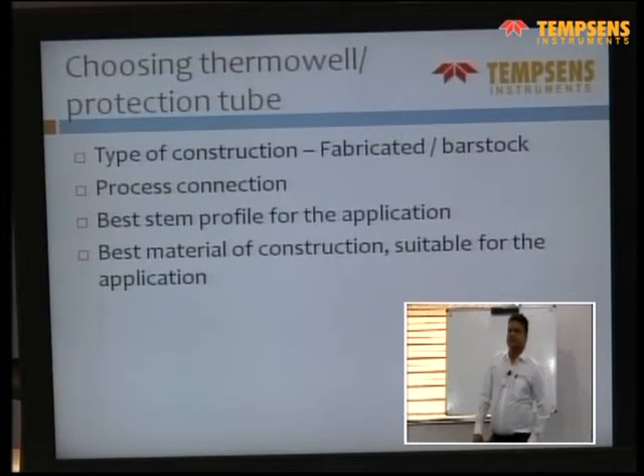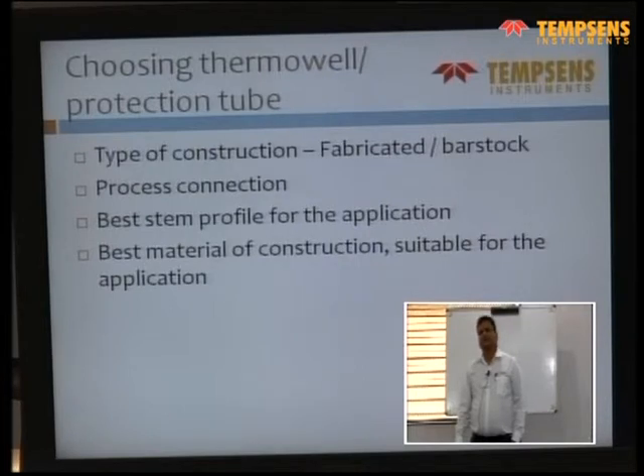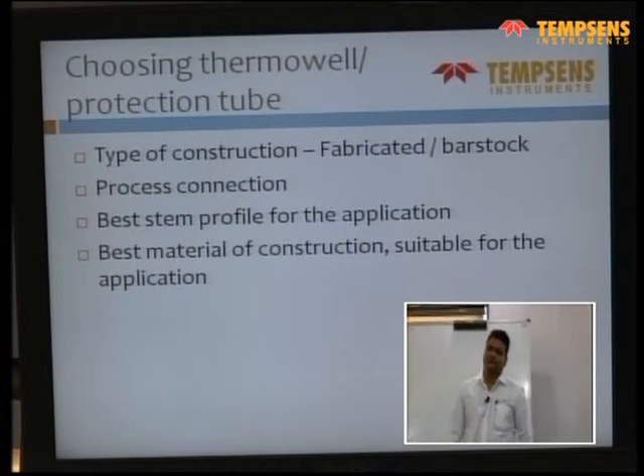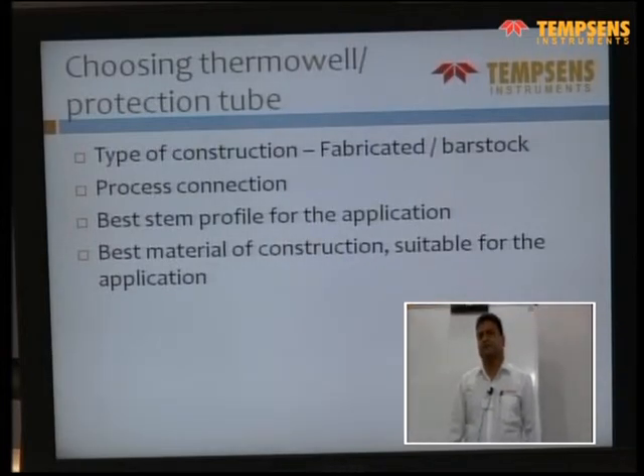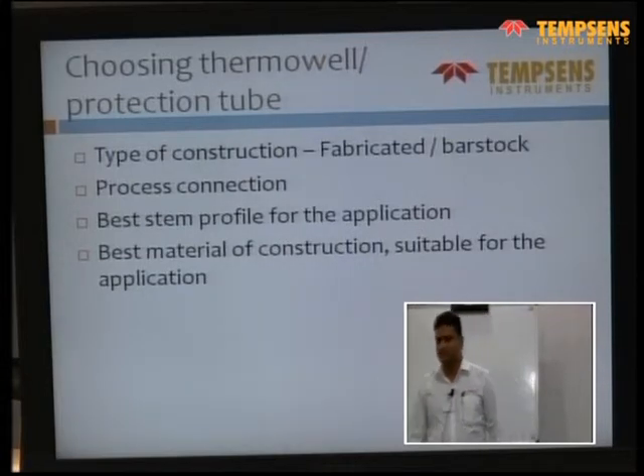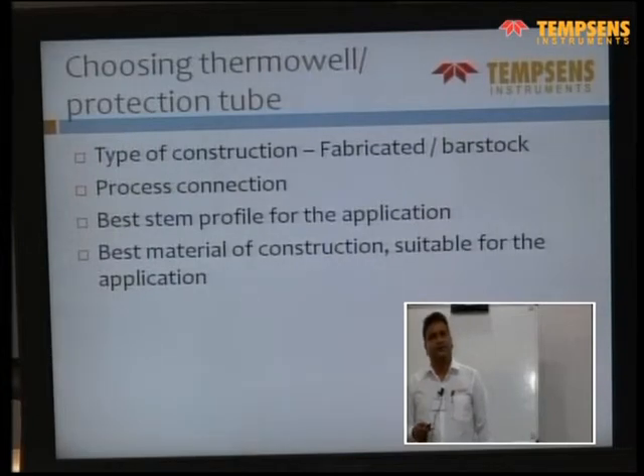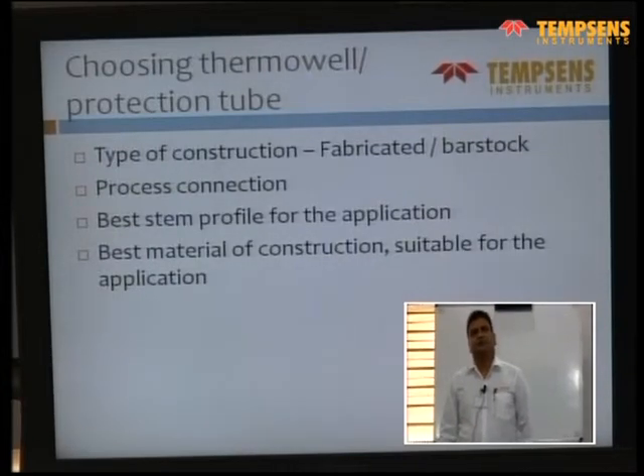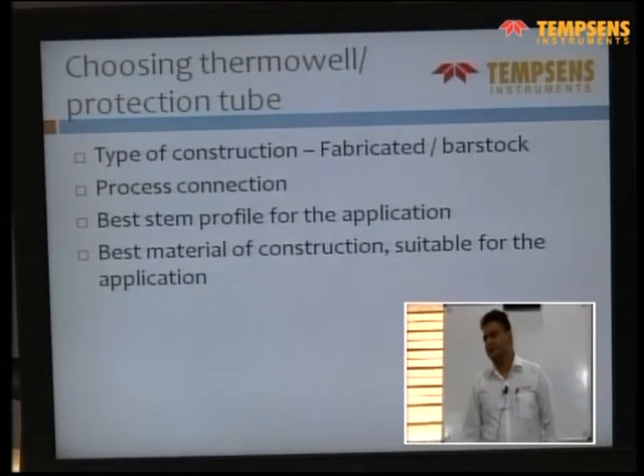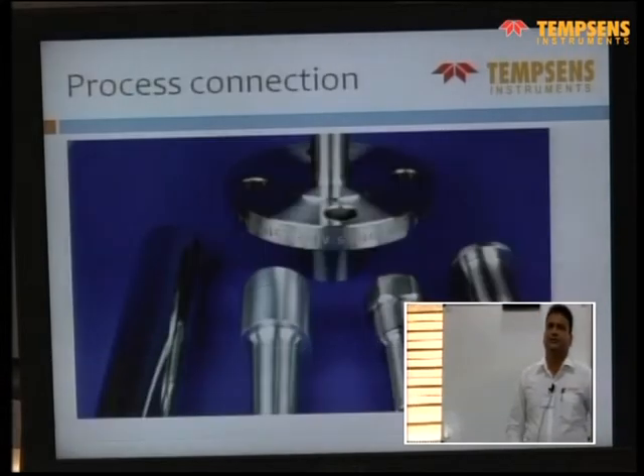The second consideration is the process connection. We'll come to it; there are different kinds of process connections. Then, what is the stem profile? This defines the response time of the sensor. Then we have the main criterion, which is choosing the right material for the thermowell. That depends on the temperature and other chemical factors. So these are the main considerations for choosing the protection tube or thermowell.